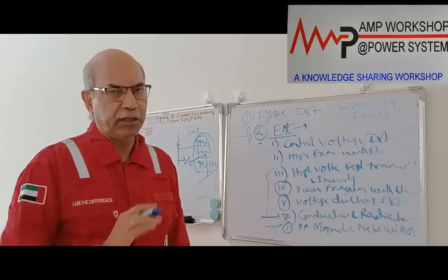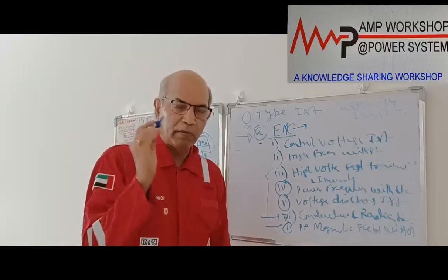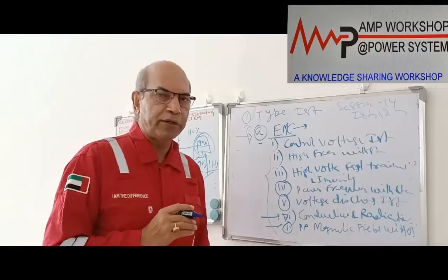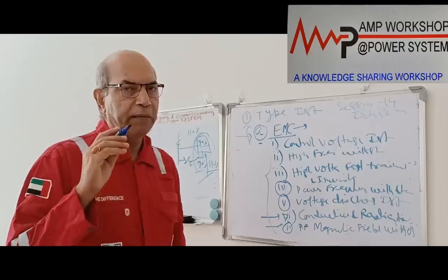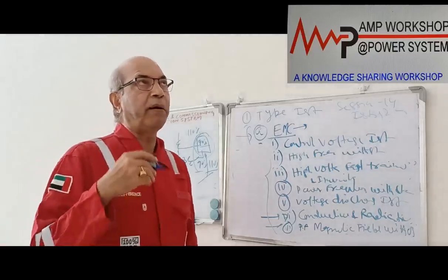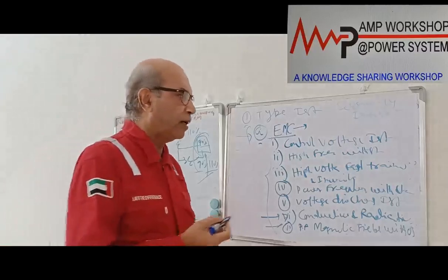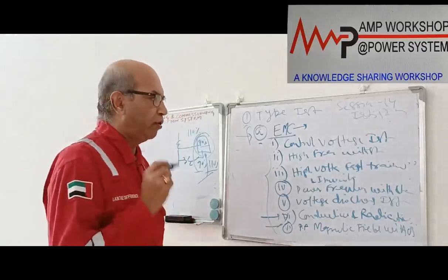This is the two-way check of the relay: when the simulated value of the various parameters is just below the tripping point, that is 90%, it should not operate under the influence of the disturbance. And if the value is 10% above the setting value, it should operate.